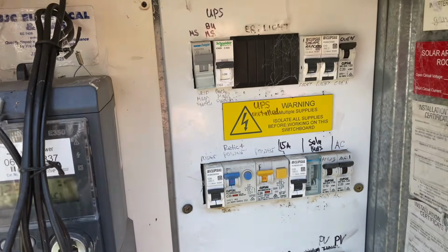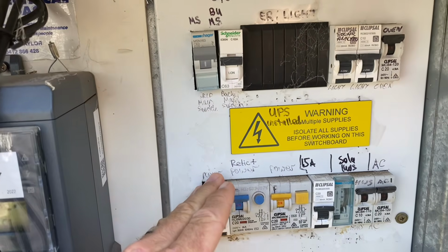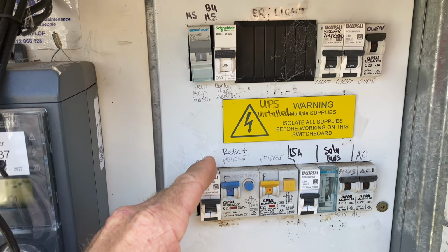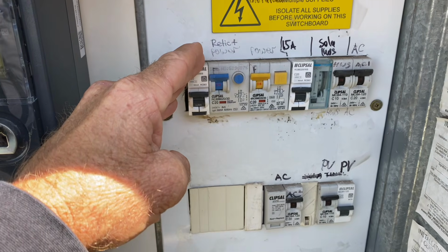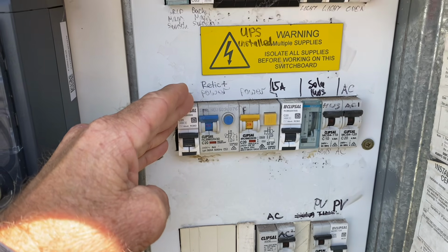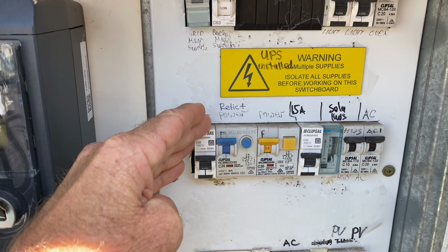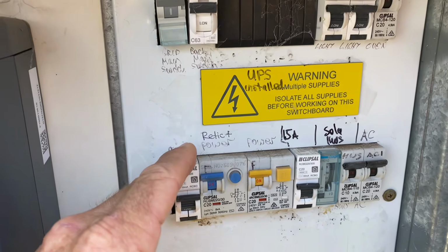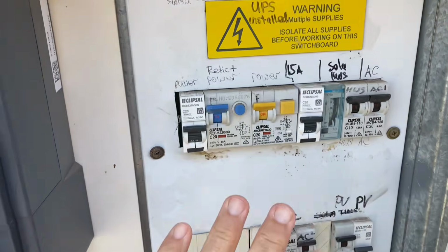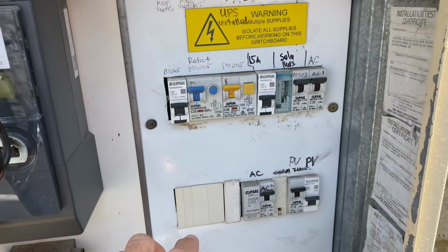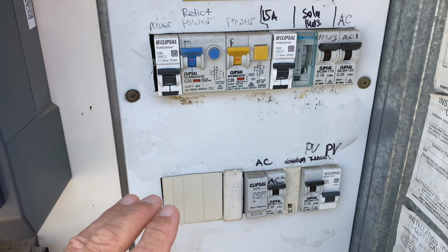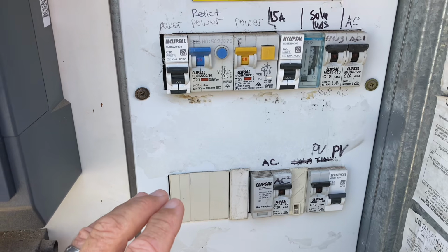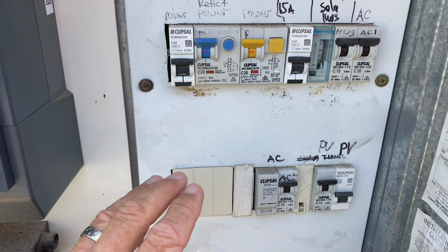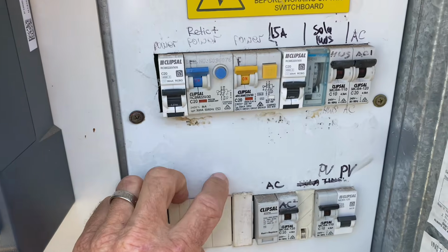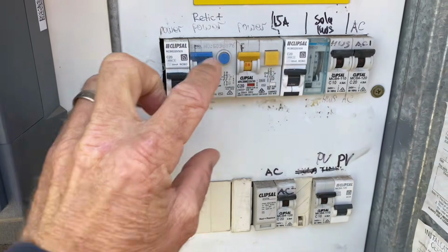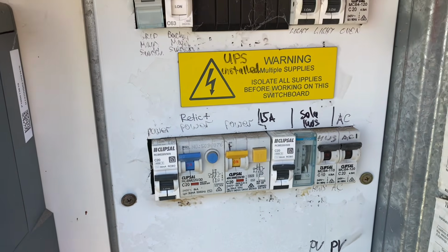So if you're having an installation done where you're not doing whole home backup, and you're just having a few single circuits on the backup supply from the hybrid inverter, then those circuits must all be grouped together. They can still be on the same switchboard as I mentioned before, but they must be grouped and clearly labelled as backup circuits or emergency power supply from the battery. They can't be one here, one there, that sort of thing - they must be grouped together and clearly labelled.